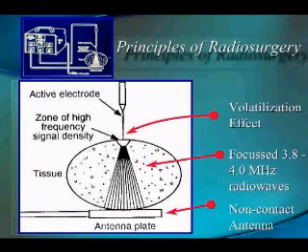through the tissue cells. The radiofrequency unit produces a radio wave that is transmitted to a passive electrode by an active one. A thin wire tungsten electrode acts as the active part, and an insulated ground plate as the passive one. The passage of high-frequency radio waves heats up the tissues due to the natural resistance of the tissues to radio signals. The destruction and volatilization of the cells at the tip of the electrode is the result of the resistance and the heat produced, leaving behind a trail of dehydrated cells with consequent production of an incision.